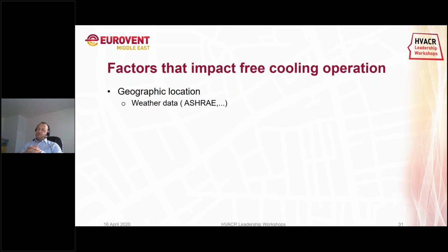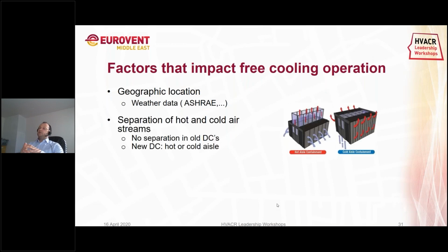If you will have a project in the Nordics, it will be much different than if you have a project in the south of Spain. It's very important to have accurate weather data. You can find it on the ASHRAE site or different other sites that are available, but it's important when you use weather data and you use wet bulbs that you have the correct data of your data center location. Next factor that can impact the free cooling, as discussed, is the separation of hot and cold air streams. You would be surprised, there are a lot of current data centers that are not having this separation yet, and there you can see very high PUEs of above 2. So this is very important to have this separation of hot and cold air streams.